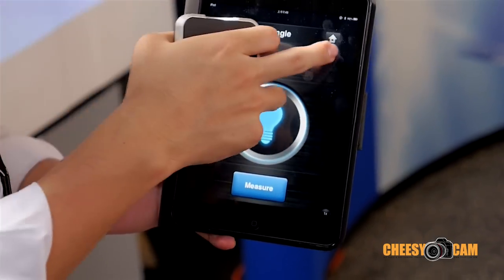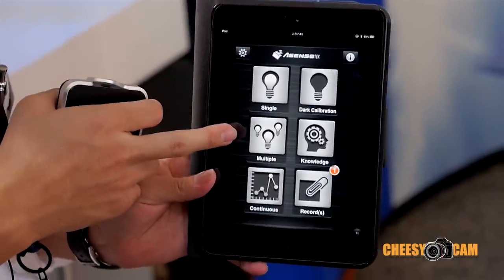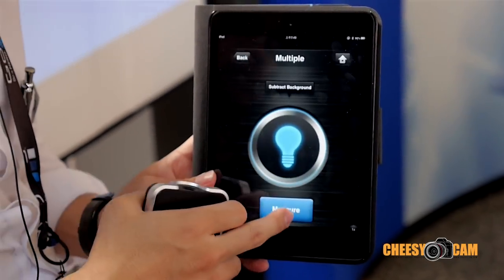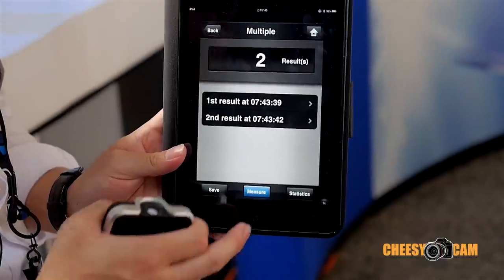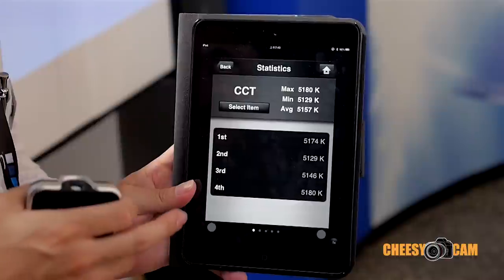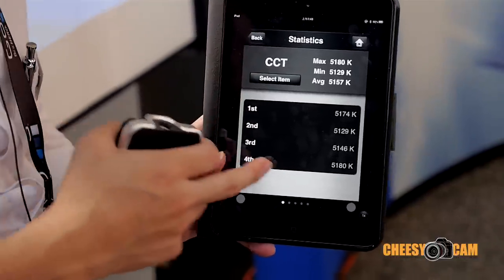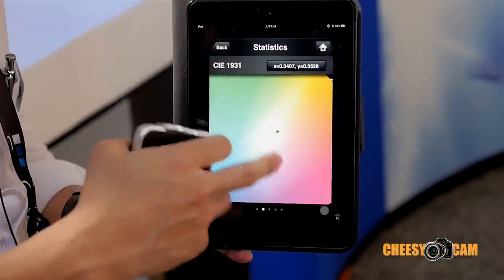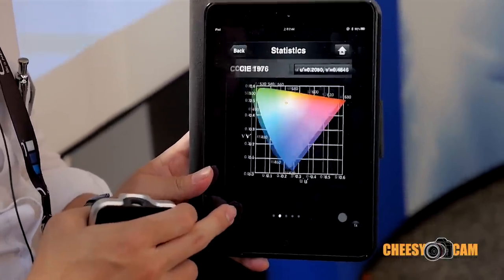We can go back to the main menu. Besides single measurement, we also have multiple measurement mode. Multiple measurement can let you compare different light sources or LED lighting. You can check all the items, start measuring, and you can get the first, second, third, and fourth measurement data. You can see the statistics to compare every parameter you want, and you can also see the CIE graph coordinates for a full data comparison.